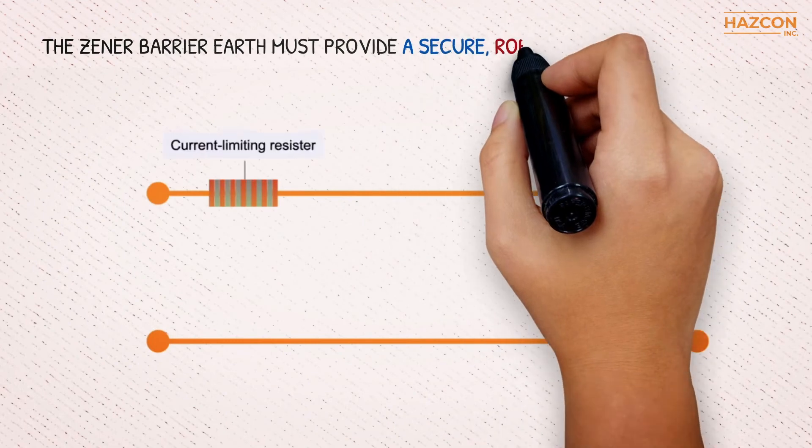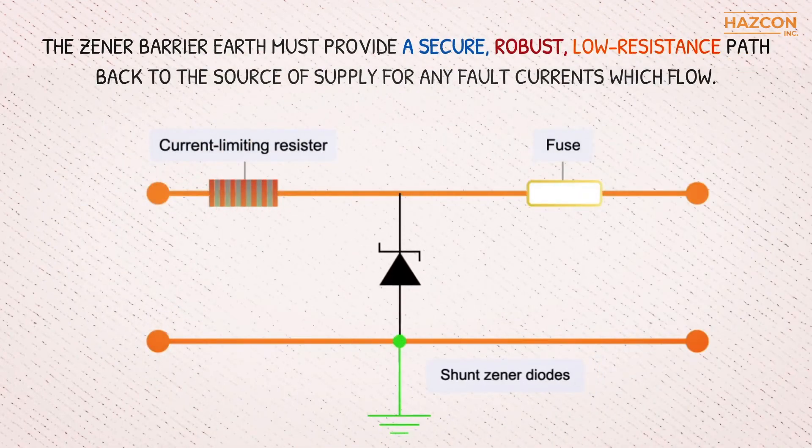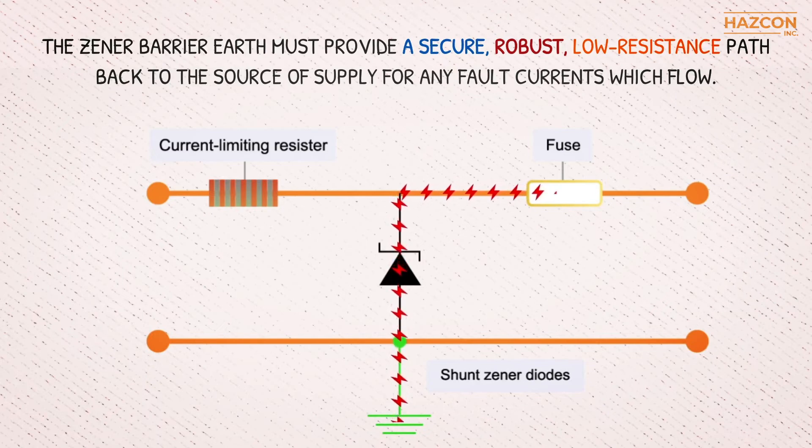In summary, the Zener barrier earth must provide a secure, robust, low-resistance path back to the source of supply for any fault currents which flow.